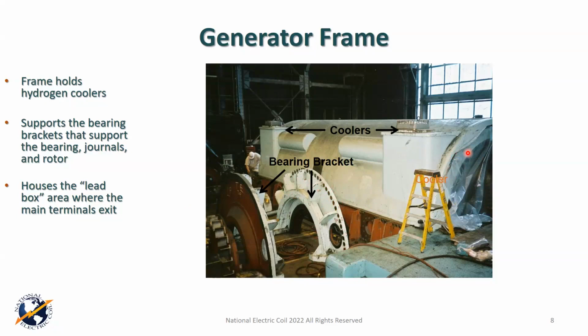It's extremely robust. As we go through and see other pictures, what you're going to learn is that hydrogen-cooled machines have to be robust because by design, they're intended to be able to contain a hydrogen explosion inside the unit should it happen. Obviously, that's not something you want to happen, but it takes solace that the machines are intended to keep that.